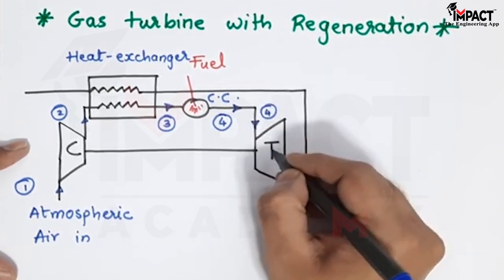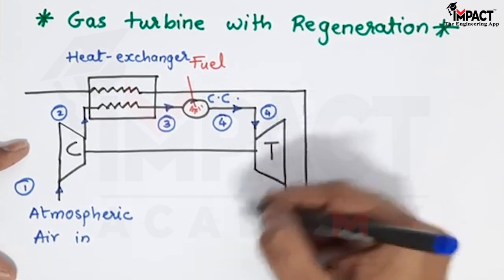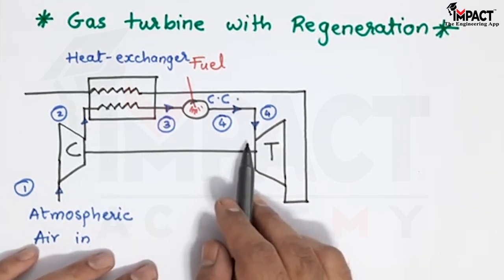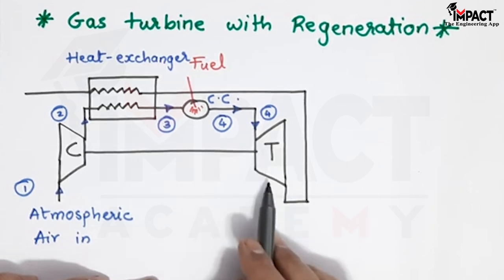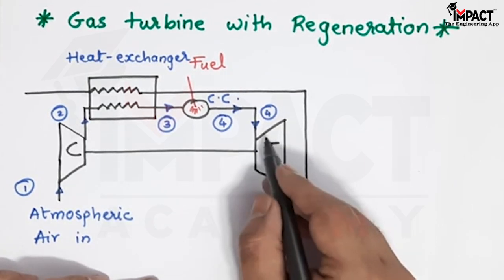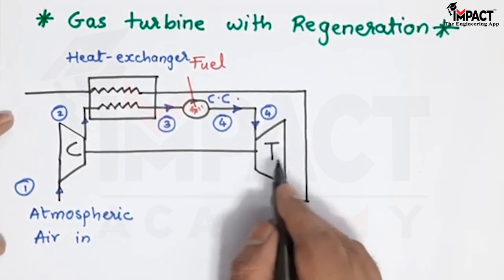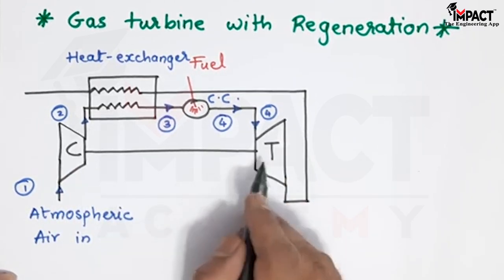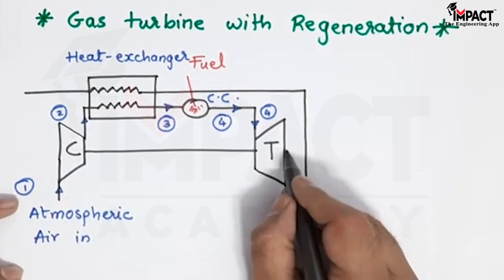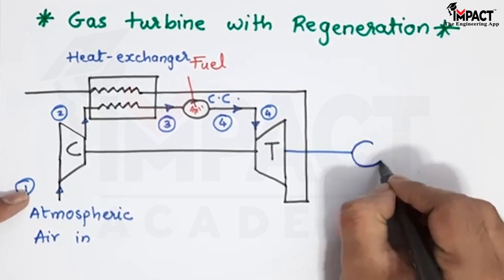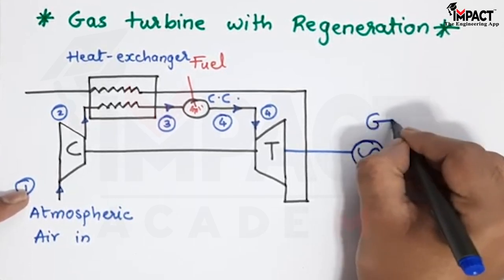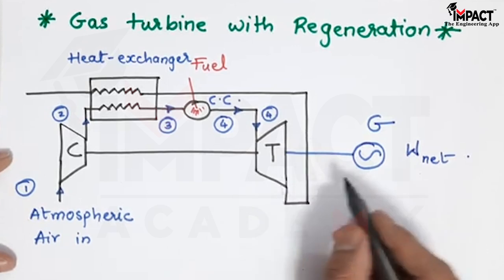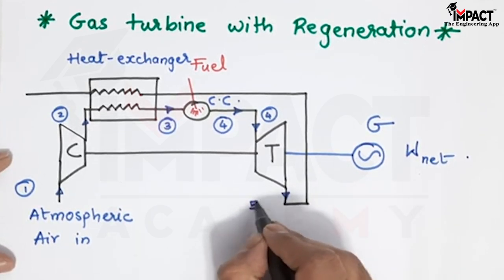That gas enters the turbine at high temperature, then there is expansion of the gases. The gases have high heat content, or we can say a high amount of enthalpy; that enthalpy gets converted into mechanical work in the case of the turbine and we get the work output. That work output is divided into two parts: one goes into driving the compressor, which is the major portion, and the remaining amount is available at the outlet as the net work. It can be used for the generation of electricity — here we have a generator — and then when the work has been produced we get the exhaust at point 5.